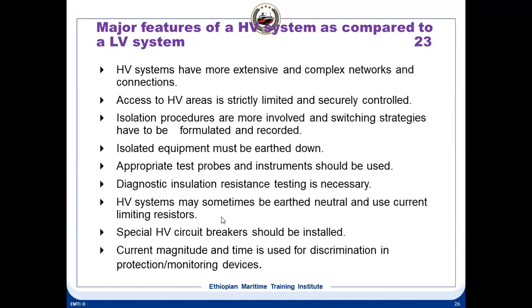Special HV circuit breakers should be installed. The high voltage switchboard uses special circuit breakers. They are vacuum circuit breakers, or SF6 type, or ACB type. And current, magnitude and time is used for discrimination in protection and monitoring devices. These are the major features.